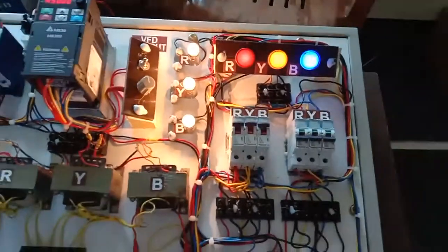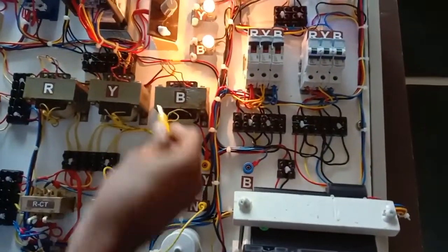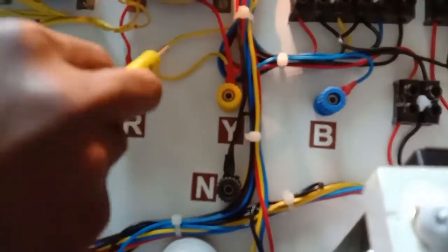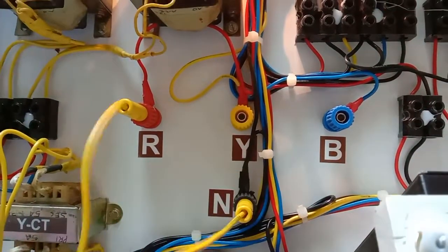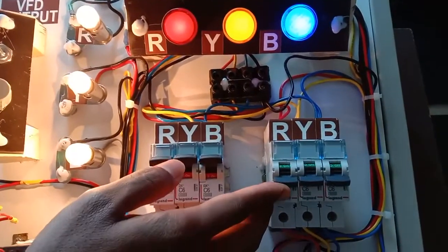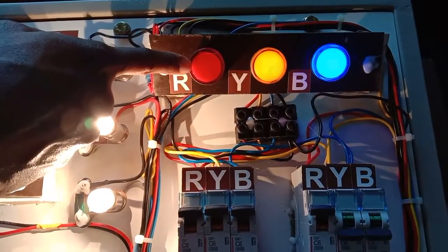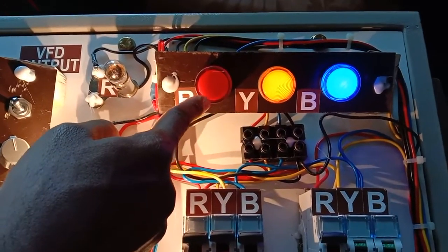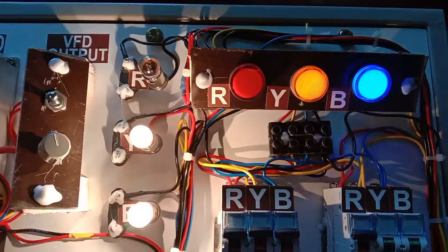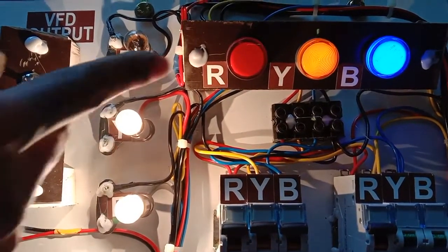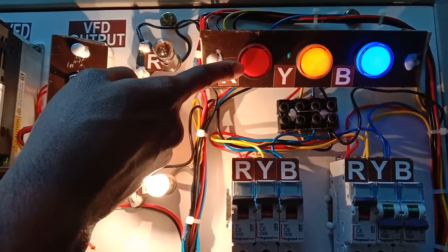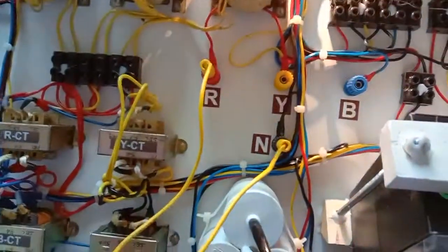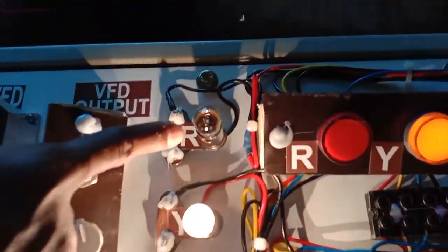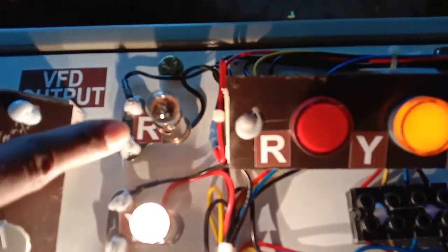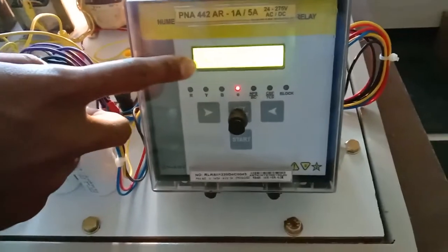In order to create the fault, take one patch cord and connect it here from R phase to neutral and switch on this fault creation MCB. So you can observe this LED indication. Now it got off. You can observe this R phase LED is in off condition due to the LG fault. And you can observe the R phase load lamp is also in off condition. Indication LED and load lamp off. And the relay is in trip condition due to the LG fault that occurred in R phase.